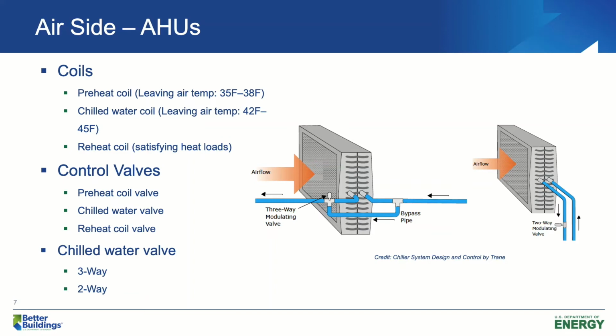We have preheat control valves, chilled water control valves, and reheat control valves. For chilled water control valves, there are 2 major types: 3-way control valves and 2-way control valves. For 3-way control valves, when the cooling load drops, the flow inside the main pipe does not change. It is constant flow, the same flow all the time. We use the 3-way valve to bypass some flow from the coil.